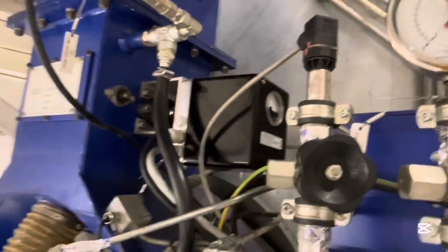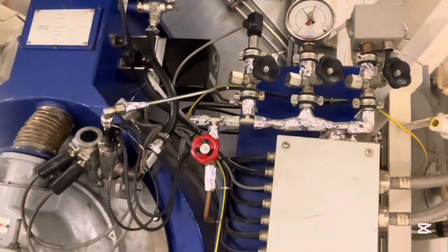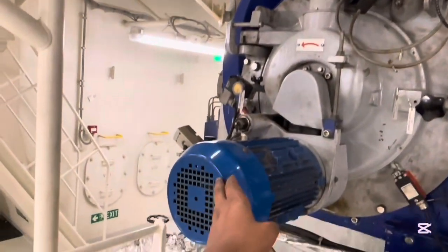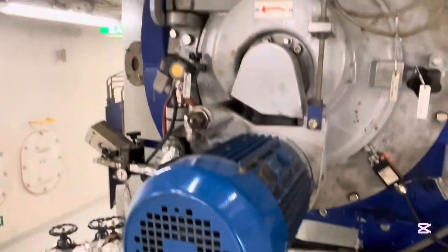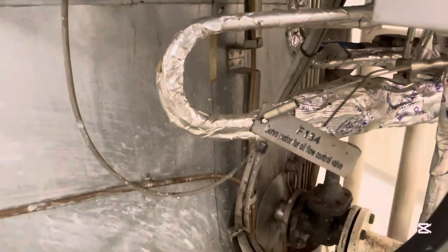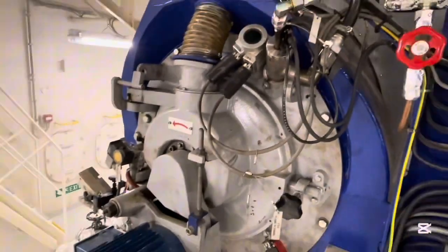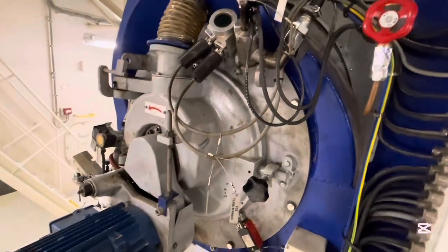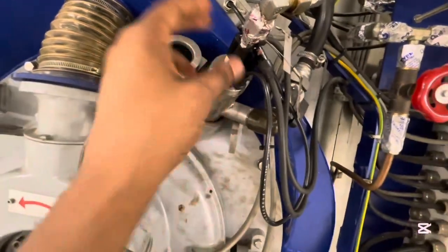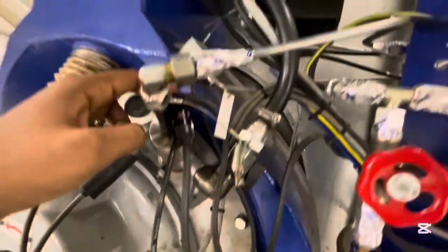So it sucks the air, and that air is controlled using that black box, that is the air servo motor. So basically from the combustion air motor, the air servo motor controls the air and sends it to the burner. This motor is the burner motor that is responsible for injecting the oil, and that oil is controlled using the oil servo motor. So the motor that is responsible for air, we saw the oil. Now we need to ignite them.